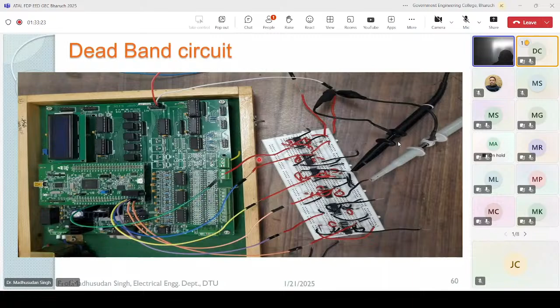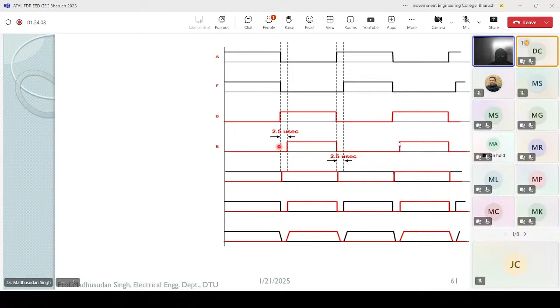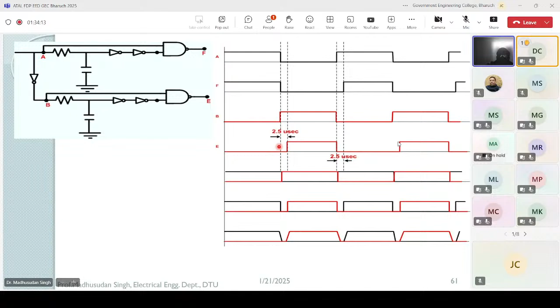These are some waveforms showing a dead band of around 2.5 microseconds between the switching of the two switches. Comparing this 2.5 microseconds with one cycle of the 50 Hertz supply, which is 20 milliseconds, you can see it is very small and can't be easily noticed when switching happens. But yes, this is sufficient to ensure there is no dead short circuit in the system. These are the internal circuits which ensure the falling edge, rising edge, and the dead band.